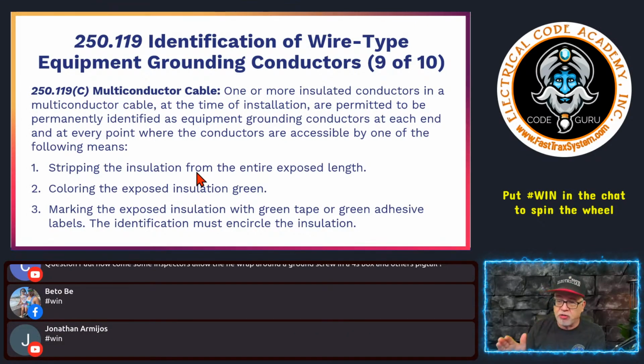Not like the 4 and larger before. This is not size specific. This is specific to multi-conductor type cables, like a tray cable, that application. It says, one, you could strip the insulation from the entire exposed length, same as you did with the 4 and larger if it was in a raceway, same here, but this is a cable. Two, you could color the exposed insulation green. So you can color it all green. Or three, marking the exposed insulation with green tape, that's typically what most people will do, or green adhesive labels, kind of the same as tape. And identification must encircle the insulation.